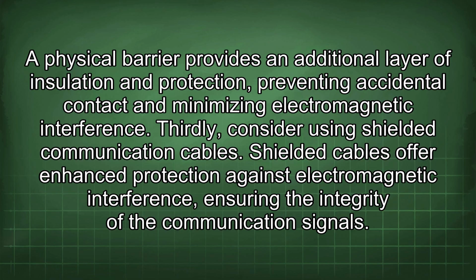A physical barrier provides an additional layer of insulation and protection, preventing accidental contact and minimizing electromagnetic interference. Thirdly, consider using shielded communication cables. Shielded cables offer enhanced protection against electromagnetic interference, ensuring the integrity of the communication signals.